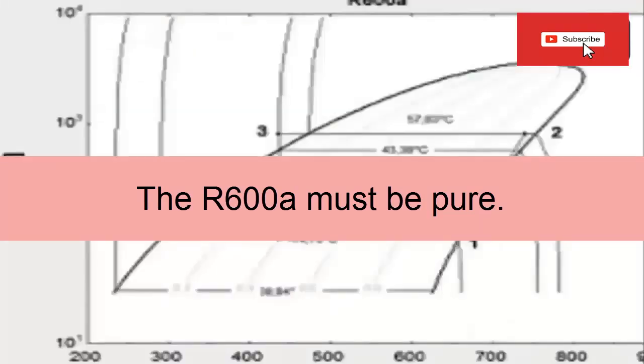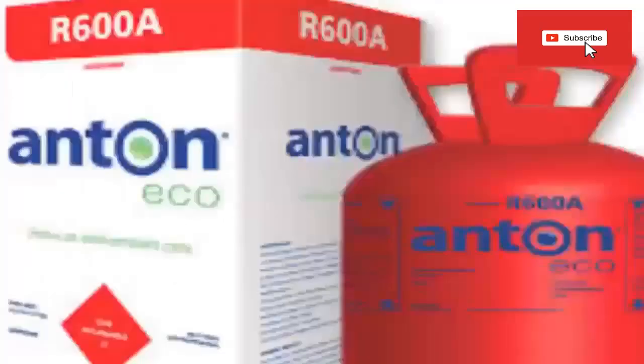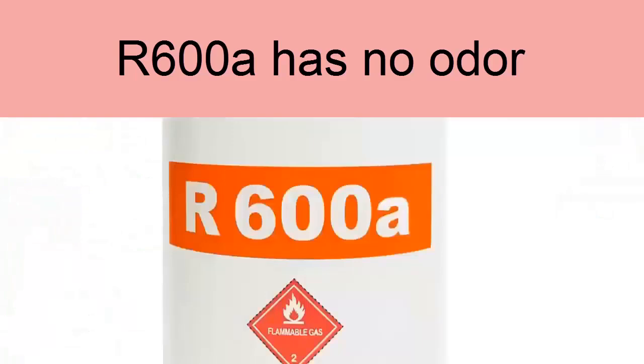It also sometimes happens that if the R-600a is not of high purity, it can be mixed with other hydrocarbons, which can drastically vary the physical and thermodynamic properties of the original refrigerant. The isobutane used in refrigeration applications is not odorized like those for domestic use, and it is not easily detectable in case of leaks.